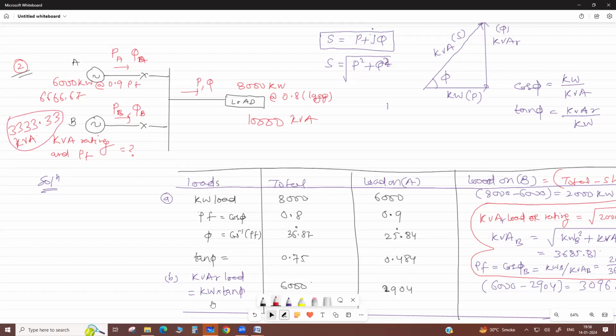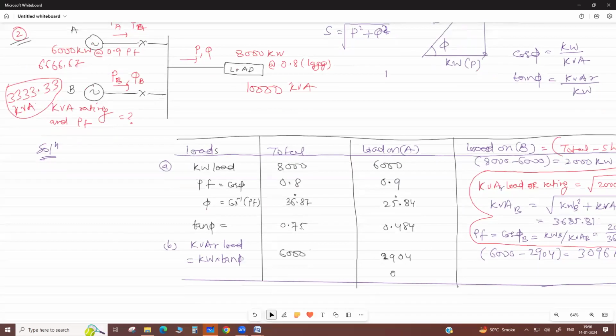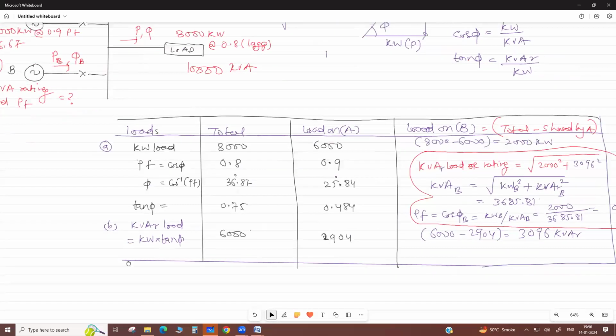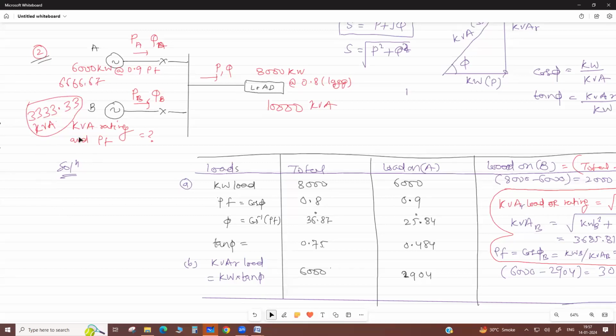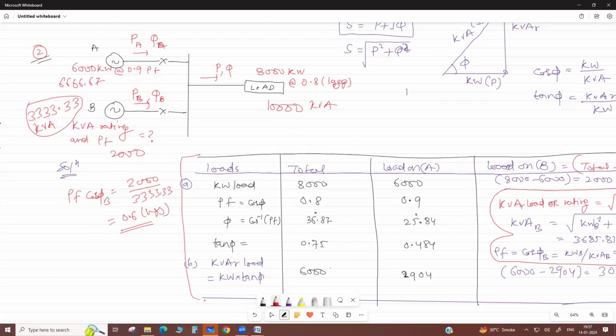So look at the difference coming here - what is the KVA rating, 3684.5, but here it is 3333. And power factor, then KVA - now you know the KVA and kilowatt also, 2000. Here the difference is, total kilowatt is 6000, that's okay, but this is wrong. Then power factor will also come wrong, cos phi, 2000 by 3333.33 will give wrong value, 0.6 will come, but that is wrong. So never adopt this shortcut method.